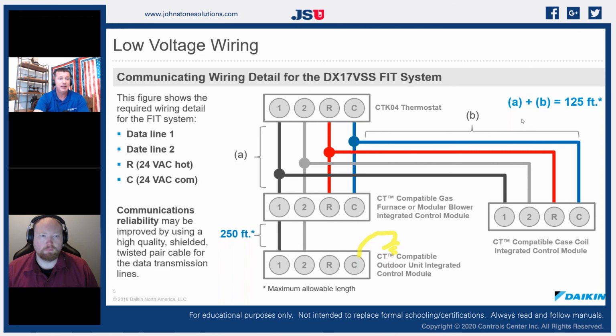So you technicians that are working in older homes that have really poor old wiring, don't be surprised to pull out an existing legacy system and put in a new communicating inverter system and the thing not want to talk properly. And then you have to go trace not only equipment, but electrical ground. I've had technicians have to go in and add grounds, because if a furnace is not properly ground, you can add ground to that. You can go find a steel water line coming through. You can find copper water line coming through. You can find a steel gas line. We can find things to add ground clamps to securely ground our equipment. So be aware that ground is going to be a whole new importance when it comes to communicating equipment.